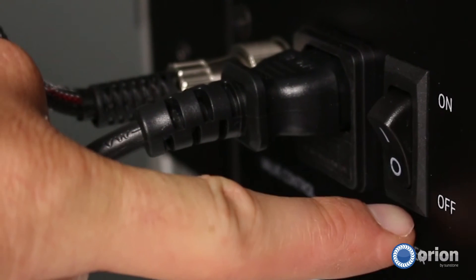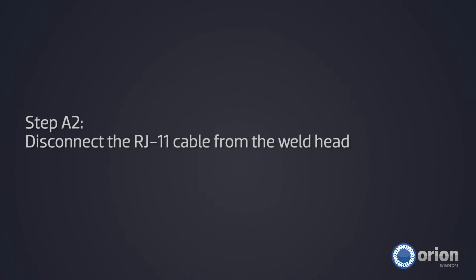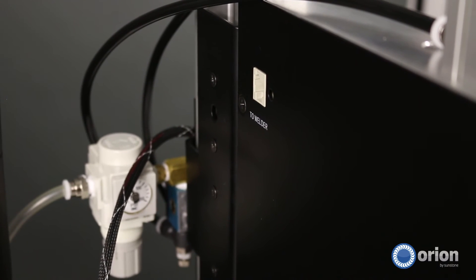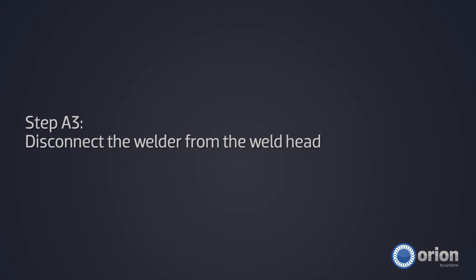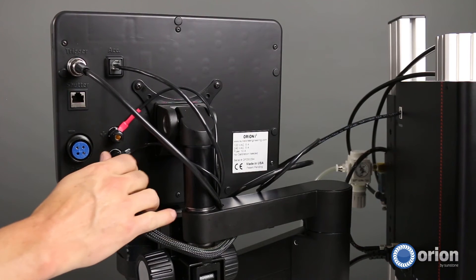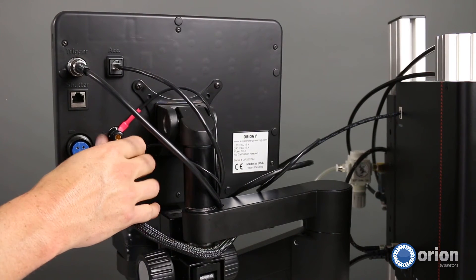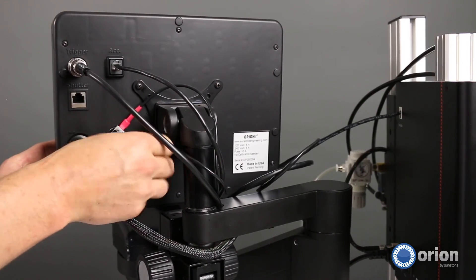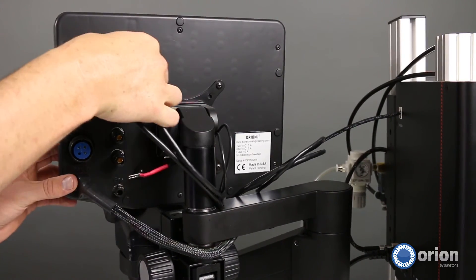Turn off the weld head. Unplug the RJ11 cable from the weld head. Disconnect the following connections from the welder. Disconnect the wires from the positive and negative ports, then unplug the RJ11 cable from the accessory port.